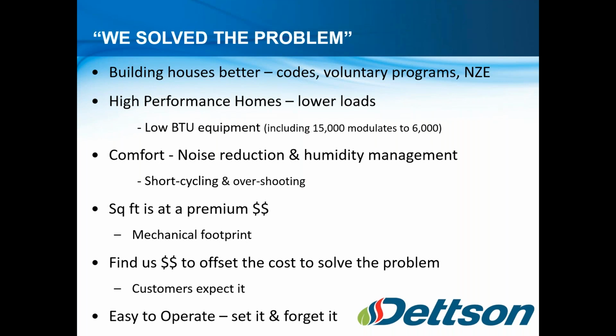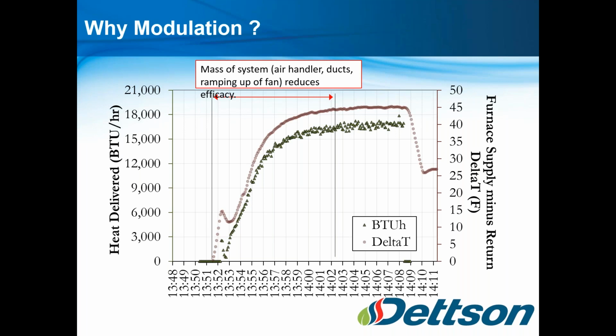So typically you might see a 30% jump from one stage to two stage and another 30% from two stage to modulation. So we've got customers expecting thermal comfort at all times, and we're helping builders get there. I always like to use the terms better, faster, and more cost efficient. More importantly, at the end of the day, we need something that is easy for homeowners to operate and not scary looking, and the whole premise that we've been hearing constantly is set it and forget it on the thermostat. So let's talk about that short cycling and overshooting.